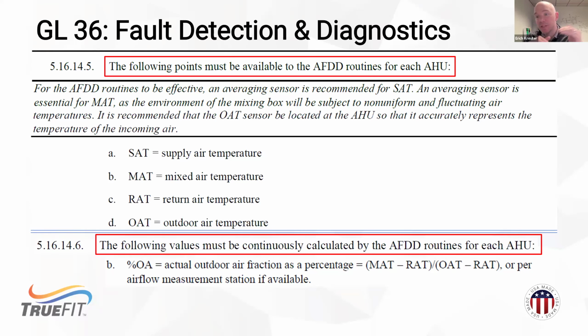If we see a split between those two numbers, my OA by temperatures does not match my OA by table, we know there's something that's mechanically changed or damaged with the equipment, and it needs to be serviced. You know, maybe a piece of cardboard stuck in the inlet, or if we lost a damper blade, or now my return damper is not moving and the actuator seized, economizer is not working. Any of these conditions will cause a split in the temperature, or the difference in the OA by temps versus the OA by table.